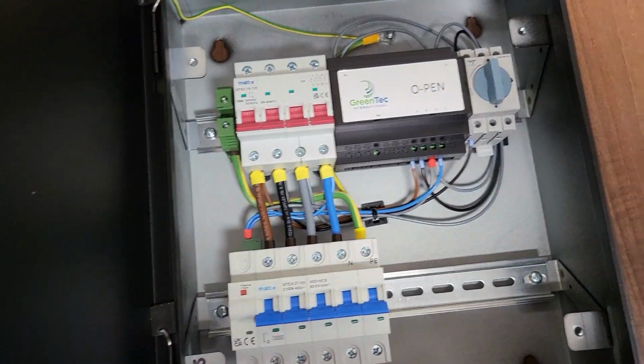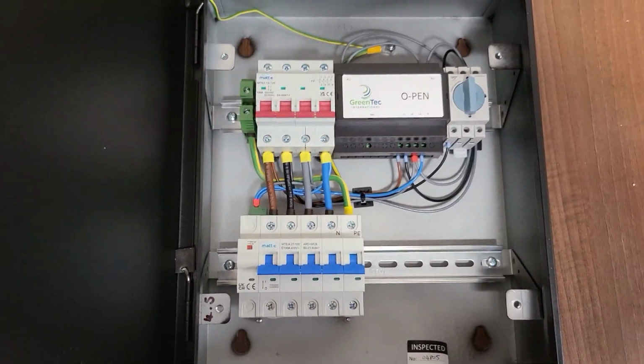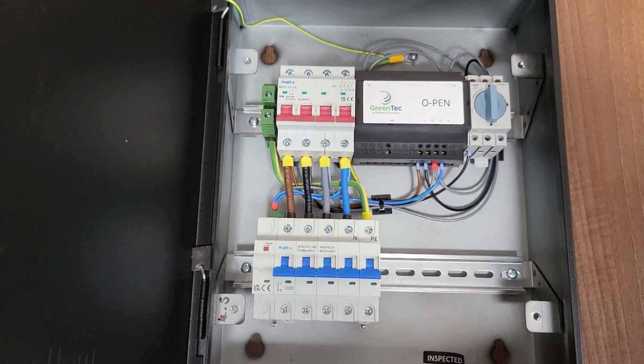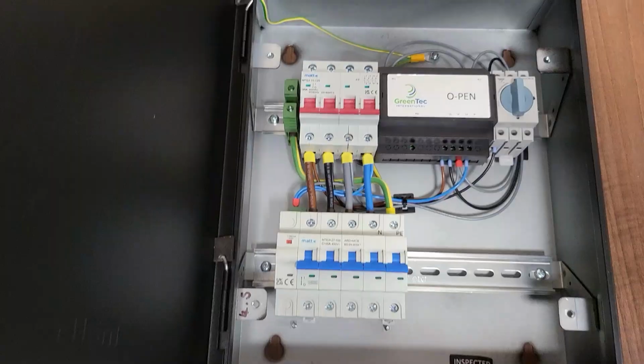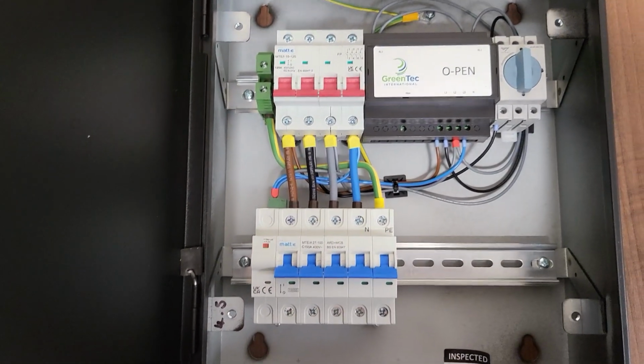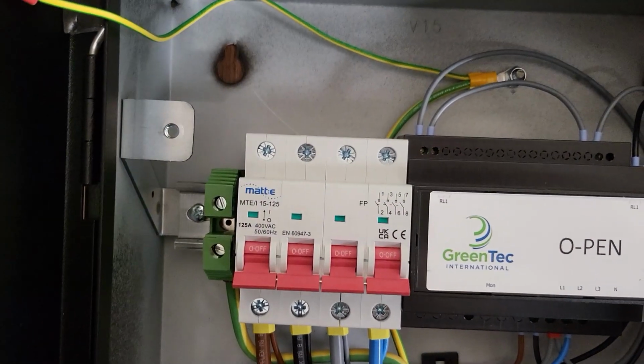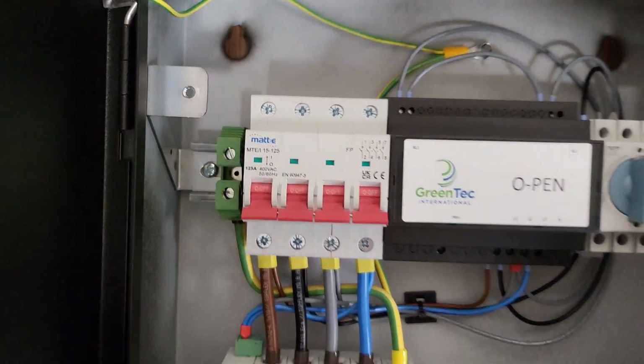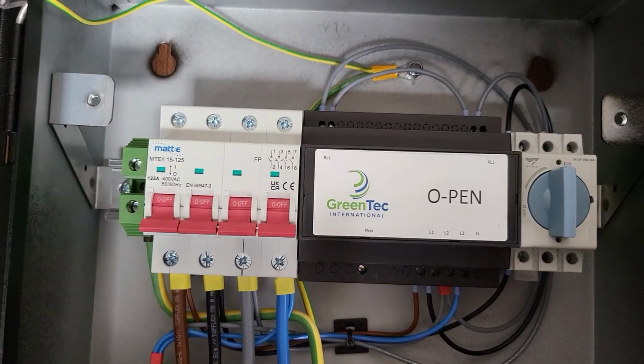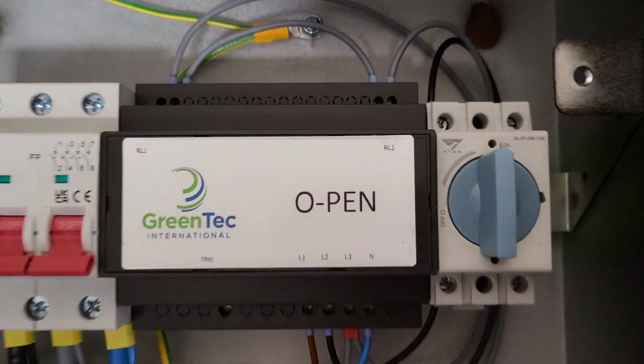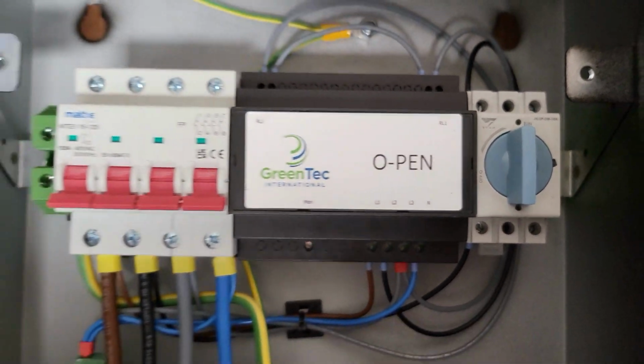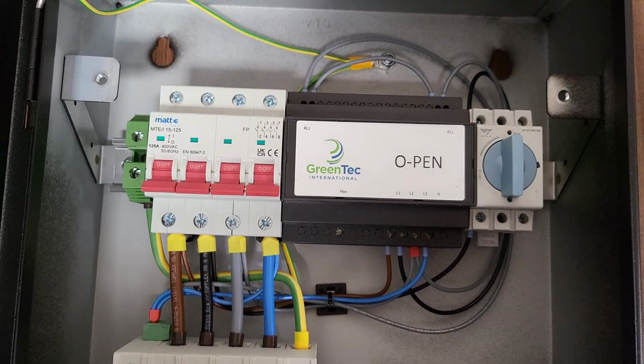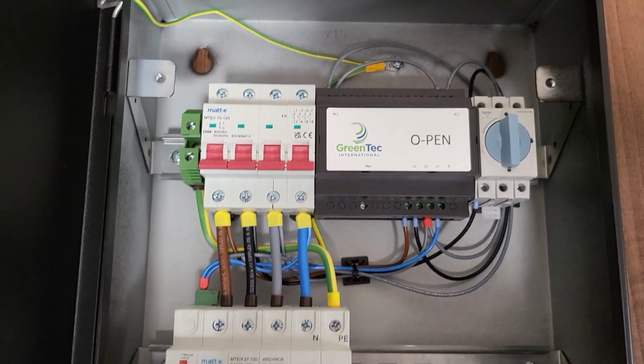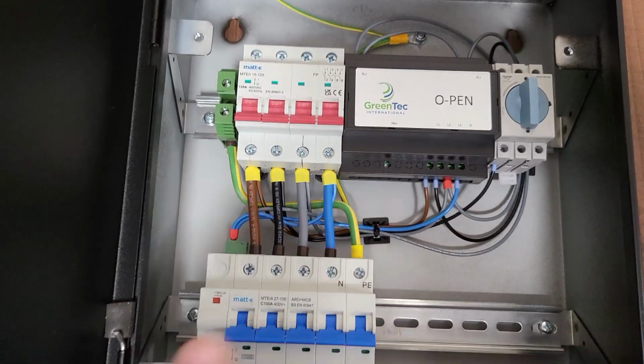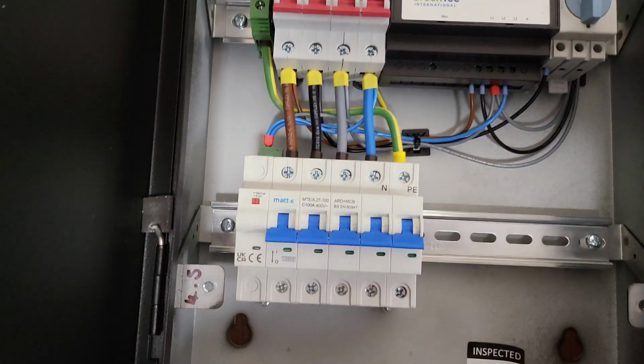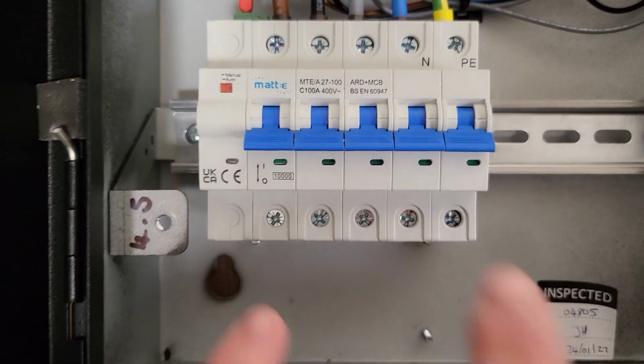Obviously, that doesn't just release away from the front of all of this. It does have screws in. I've taken them off to speed up the video. So you'll see inside here, we've essentially got the main switch at the top, which is where you bring your incoming cables into. You've got the magic that does the pen fault detection, a little test point here where you can activate the pen fault, and we'll go through that in the manual, but basically it disconnects L1 to make it see a loss of a phase, and it will put everything into operation, if you like, make the magic happen.